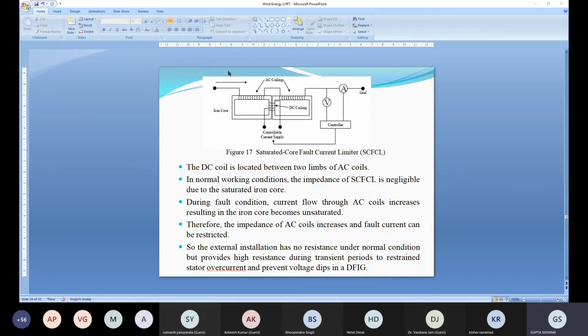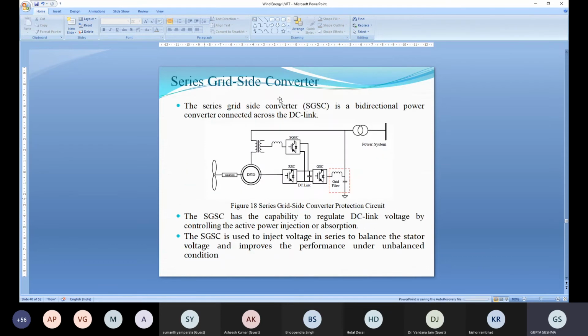Here we have two coils, AC coils and DC coils. Under normal condition, the impedance of this coil is negligible due to saturation. But as soon as there is an overcurrent, this core will be unsaturated and offers high impedance. And when it offers high impedance, current will be restricted. So this is the first, superconducting fault current limiter. Second is the saturated core fault current limiter. Next and last is the series grid side converter.